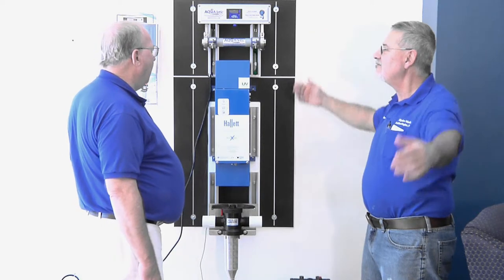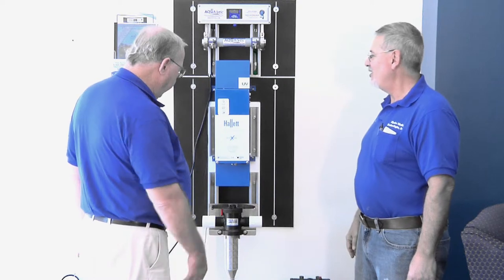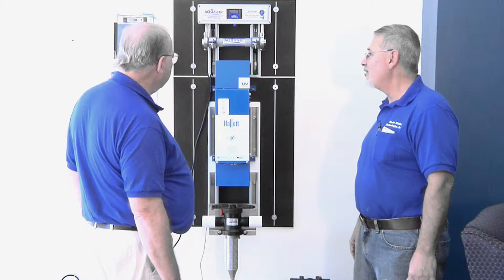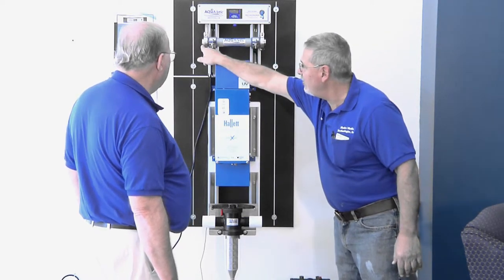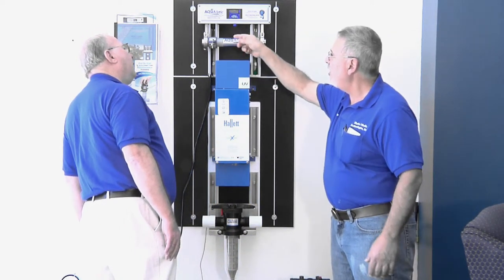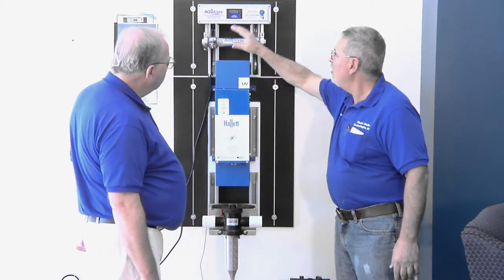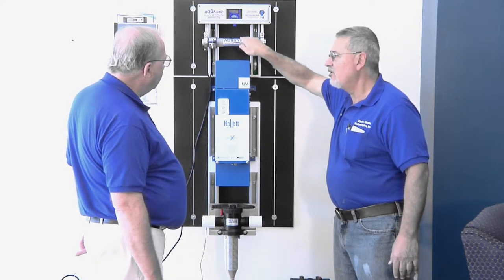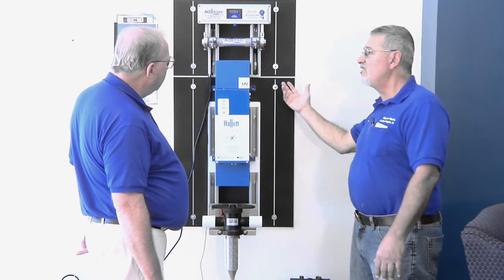This is it. You've got a controller and a piece of pipe in this blue box. I've seen these filters before, but it doesn't look like it's anything special. It is. This is stainless steel — take a look in there. You see the baffling in there in the middle? What's happening is that water is coming through here, creating a turbulence along with the electric charge. The electric charge is adding electrons in here, changing the molecular composition of the hardness ion. It comes out here and it's not going to stick to anything.